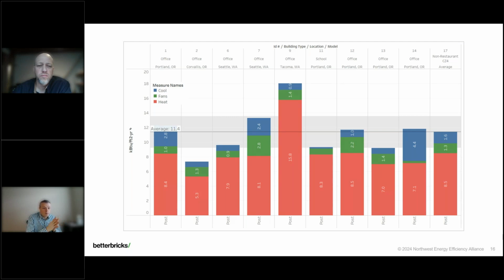It's important to note that while I'm focusing on this climate zone 4 project, the colder climate projects in Montana and Eastern Oregon were also very successful, averaging 50% HVAC savings. The potential for savings is even higher in absolute terms because of the magnitude of heat loads. Heating is the largest chunk here; cooling and ventilation matter, but heating is biggest, so in colder climates the heating side can provide even greater savings.